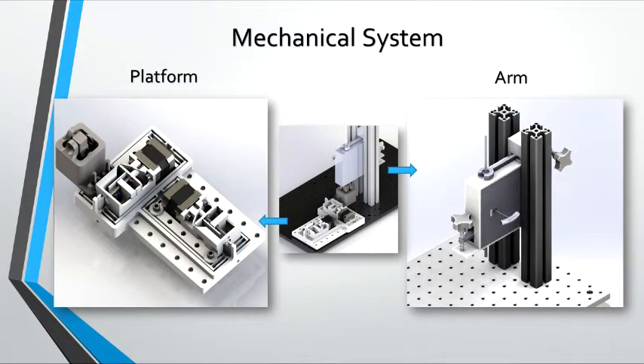We have separated the platform into two parts to decouple movement from certain aspects of calibration. The platform is entirely responsible for movement and for calibrating the test chip so that it lies flat with respect to the laser head or the light probe. The arm is responsible for rotating the probe to align with couplers on the chip and to adjust the distance between the test chip and the probe.